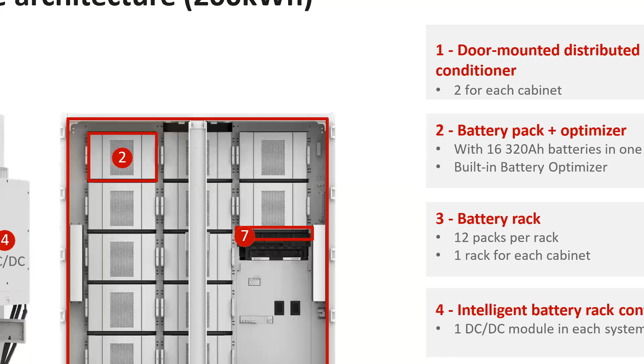Yeah, this is the 2 megawatt hour energy storage system, just like the 200 kilowatt hour. The difference is that there will be more battery packs and battery cells in this. The number of air conditioners will be from 6 to 12, and there will be 16 to 18 cells in the pack, which has a built-in optimizer as well. There will be 21 battery packs per rack, and 6 racks in this energy storage system. The size will be 20 foot, it is a lithium iron phosphate battery type, and the weight will be almost 30 tons.